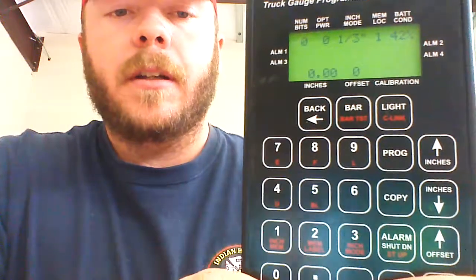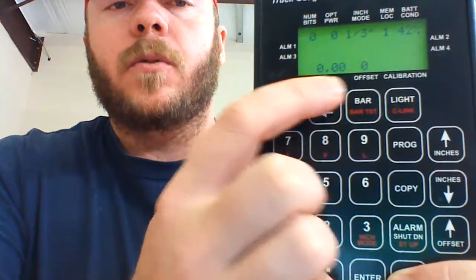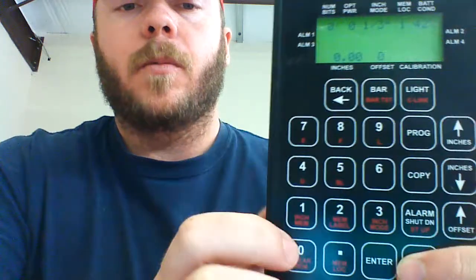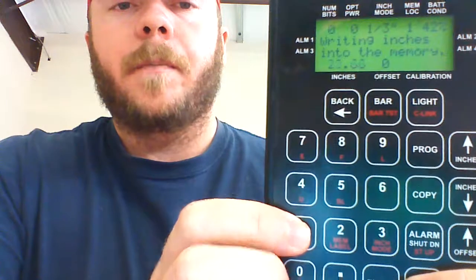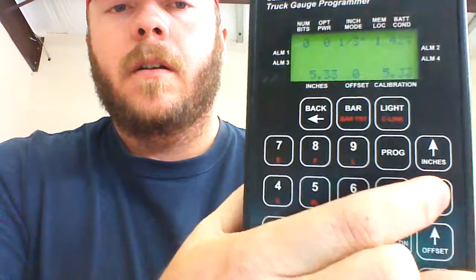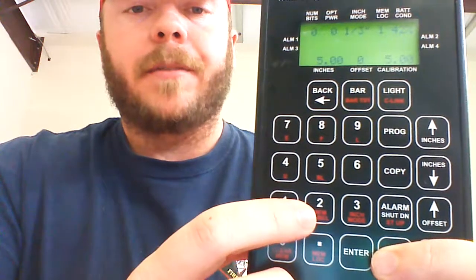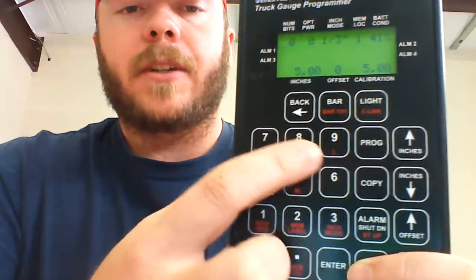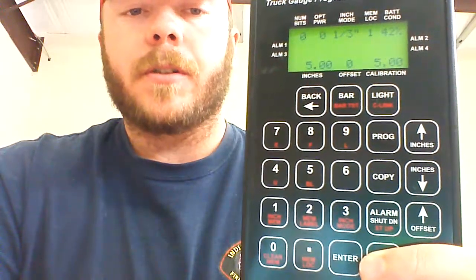One thing I use quite often in testing is inch to memory. What this does is it takes and stores into the calibration side the inch values, just to have a value over there. So I hit the shift key, inch to memory, and it's going to write the inch values over to the calibration side, and I can inch up and down and you can see those values there. Memory label, it's not something I've ever used, but you can label the memory locations with a letter. I've never actually done that. I have a note down to let me know what I have in my memory locations.